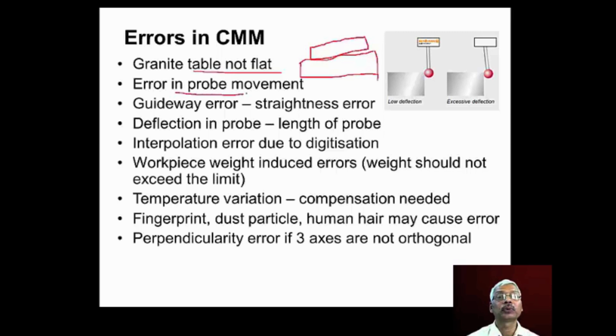And error in probe movement: when the probe moves in the x, y, z direction, there may be some error in the guideway. The guideways may not be straight, or they may not be moving along a straight path. Because of this, there will be error in the measurement. And then deflection in probe. If we use unnecessarily long probes, they will bend too much, and because of this deflection, error is introduced.